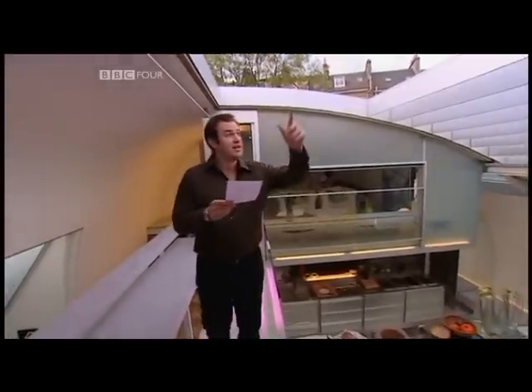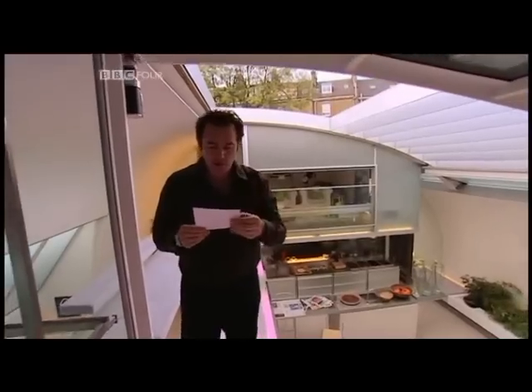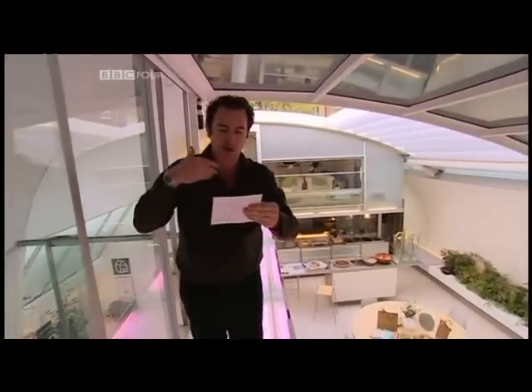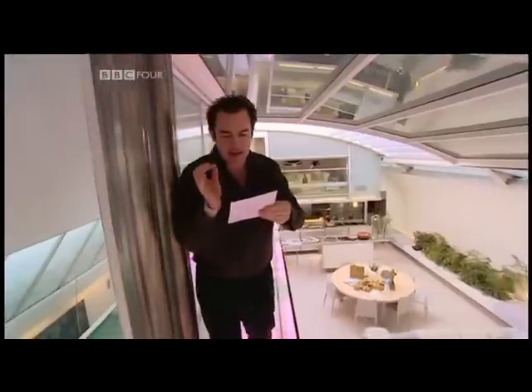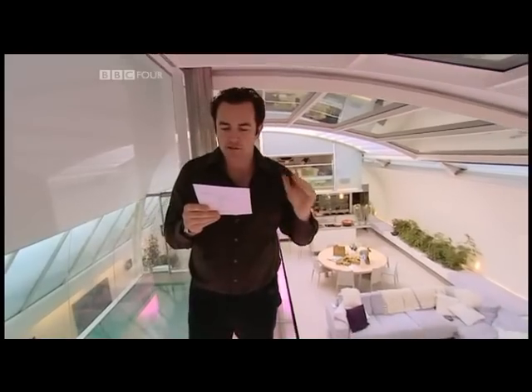And this house actually has natural ventilation, used to control heat gains, a rainwater storage tank under the building that acts as a thermal buffer, underfloor pipes providing heating and cooling throughout, passive solar collection within the roof, Low E argon-filled glazing that reduces heat loss through the glass. Heat recovery mechanical ventilation units extract from the bathrooms and provide a preheated or pre-cooled fresh air supply into the bedrooms and living space. There's computer and audio-visual wiring throughout, obviously.